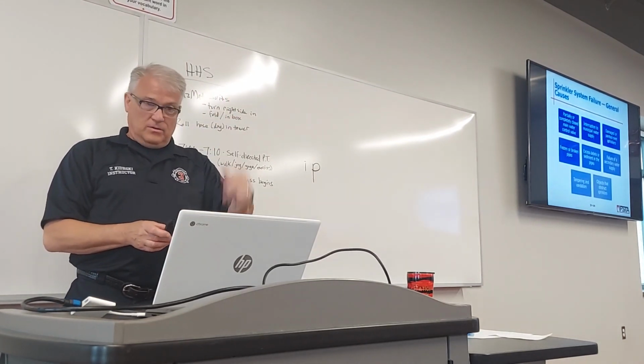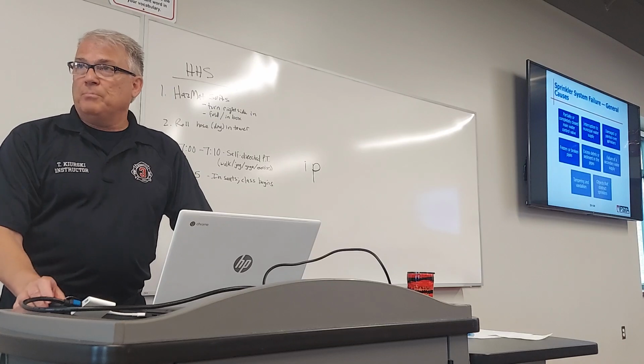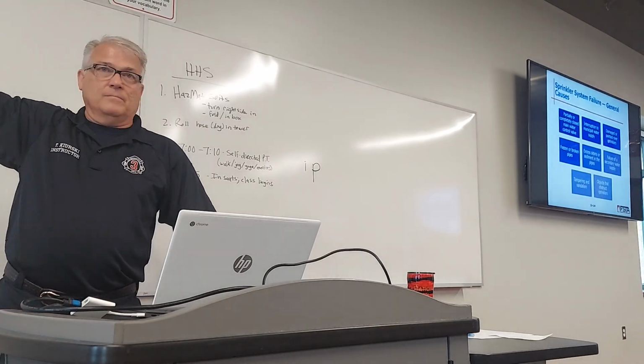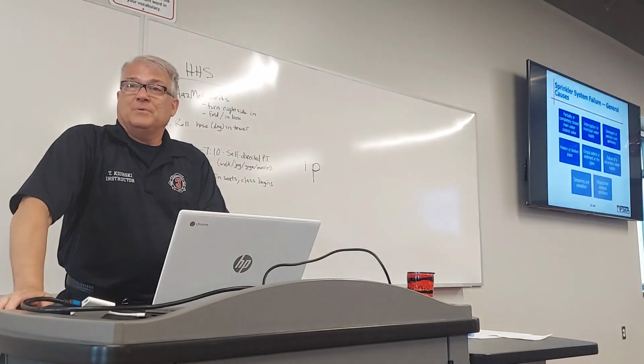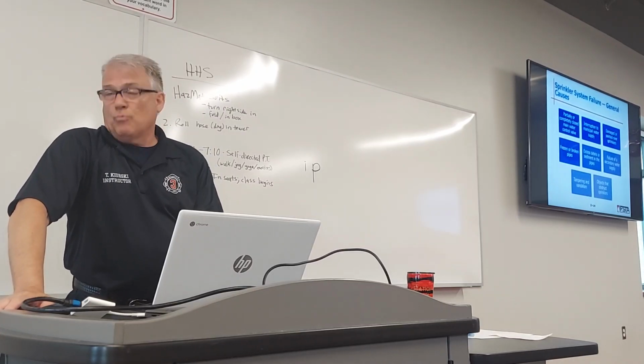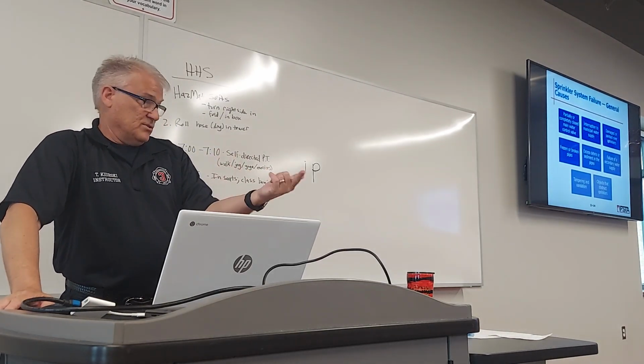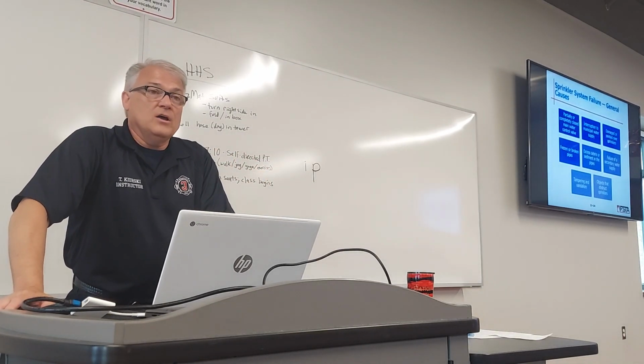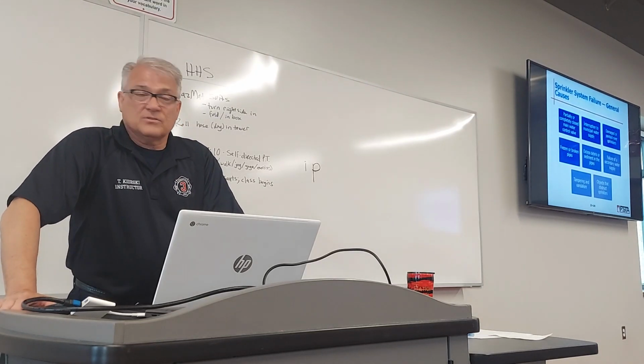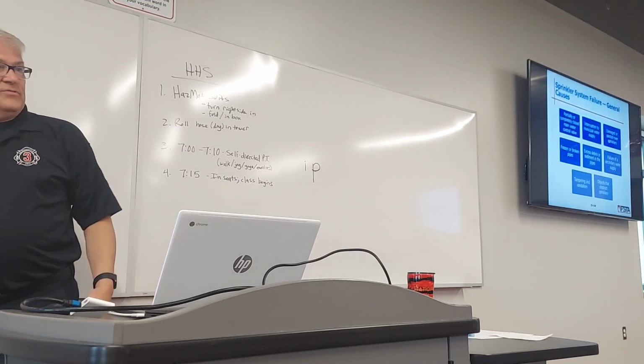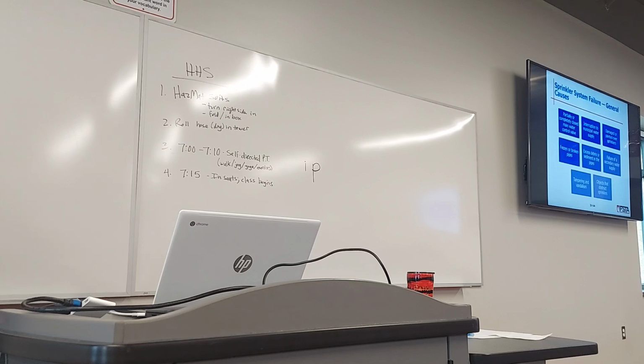Sprinkler system failures, general causes: people. That's the general cause. People doing stupid things, like arsonists who want to burn the building, so they research how to shut the system off, and they shut it off. Or people doing dumb things, like, oh, I work at this facility, and there's a door that says fire sprinkler control room over here, and there's a fire going on in the employee cafeteria right now.